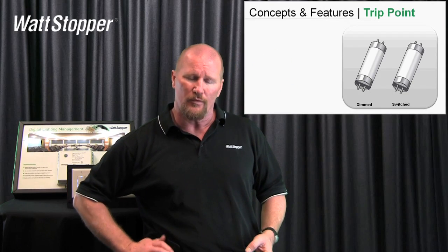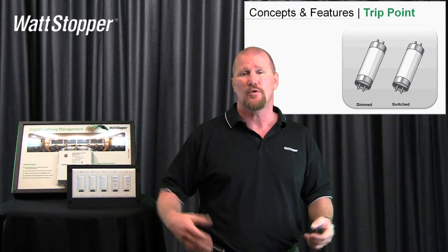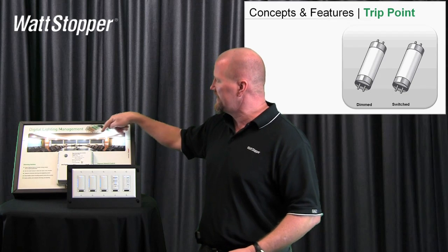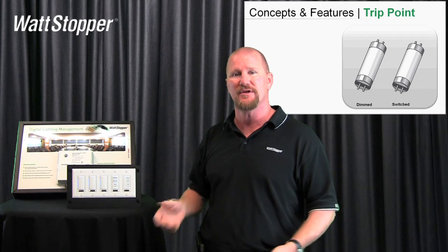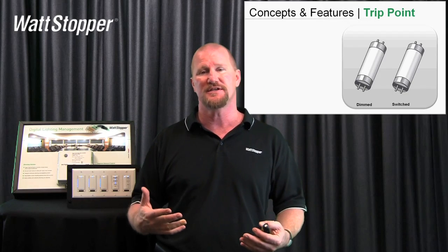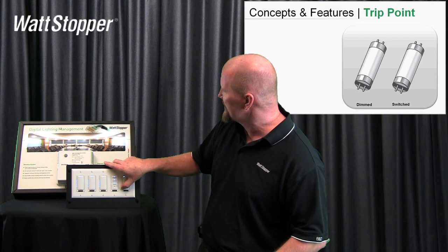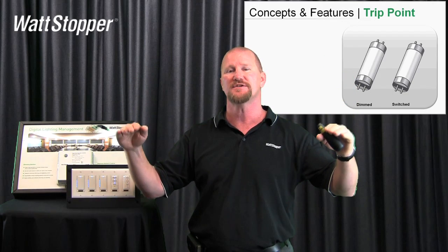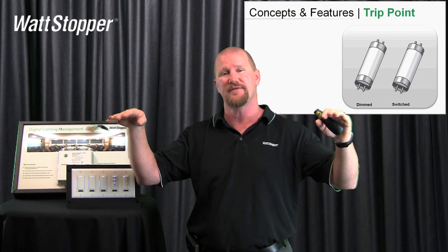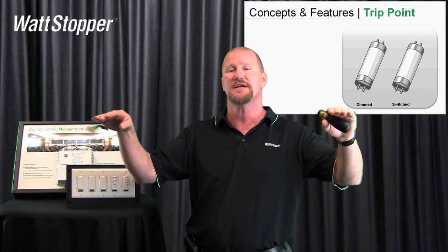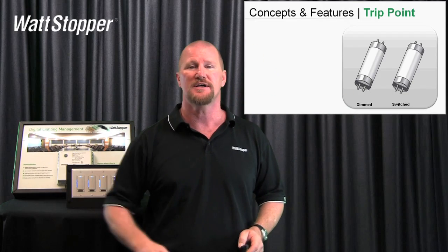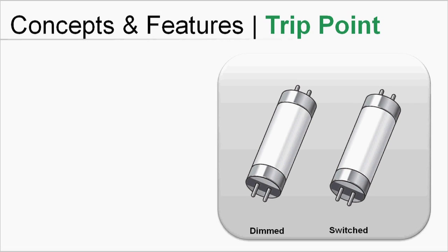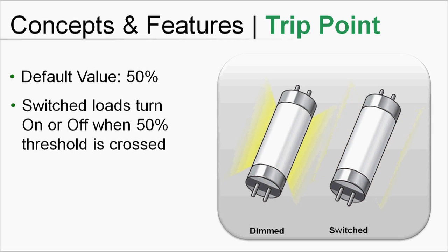The reason you'd want to adjust trip point is to choose when in the ramp or fade you want that switched light to turn off. In my conference room example, if the cove light accounts for about 80% of the room's light and doesn't turn off until I dim all the way to the bottom, I wouldn't have much effective dimming. So as I ramp down, the down lights and sconces dim, and when they reach 50%, the cove light switches off — leaving me the bottom 50% of the down lights to adjust. On the way up, when they reach 50%, the cove light turns back on. The important thing is it's totally adjustable and customizable by you.